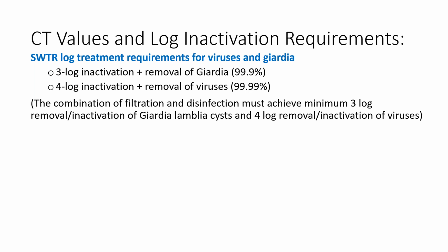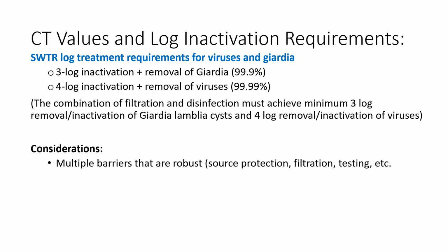The compliance is achieved by a combination of the two, removal and inactivation, or filtration and disinfection. So total. And there's some considerations though to mention. So you notice if it's either or it's a combination, you could achieve all of that with inactivation, or you could achieve all of it with filtration theoretically. But that probably would be a problem if you were just leaning on one or the other, because you'd be depending on just one barrier, and you want to make sure all of your multiple barriers are robust. So you have a robust removal, you have a robust inactivation. And speaking of multiple barriers, you have source water protection, coagulation, flocculation, filtration, disinfection, and then finally testing and protection of the water system from sanitary defects, because your operators are out there monitoring and repairing.